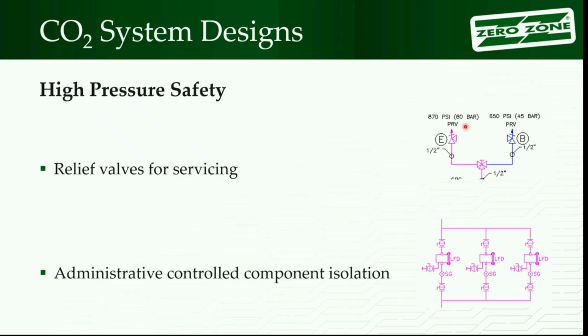So let's say you had a solenoid valve and you had EEV valves. Solenoid can shut off, EEVs can shut off, you would see a check valve then, right? From our company, you'd have a check valve, because those can happen automatically. You're not having a technician go out there and close them. It happens. That's what the software is supposed to do. It shuts it off. We don't want to trap that liquid and have it move with that. So those will be in there, but it is paying attention to what you're working on.